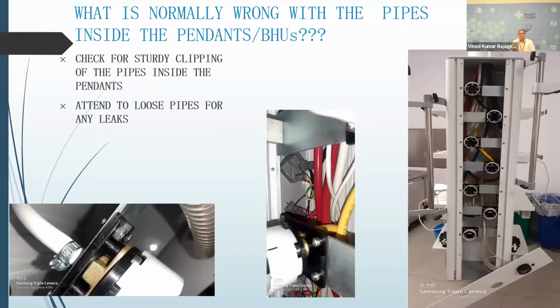Coming to the pendants, in the medical care areas these pendants have a lot of electrical outlets as well as a lot of medical gas outlets. Now you need to have a partition between the two. Number one, you have flexible piping connecting the rigid piping from the ceiling to the outlet which is fixed on the medical gas pendant. This flexible piping has to be properly installed. Number one, the clipping at both ends has to be proper, and the piping pressure tested and leak tested so that there is no leakage. There should be regular preventive maintenance in this aspect because many of the pendants are movable, some of them are rigid. But when they are movable, obviously the movement of these flexible pipes inside the pendant will be a critical issue where leakages could happen because the unclipping of these clips will be a problem.